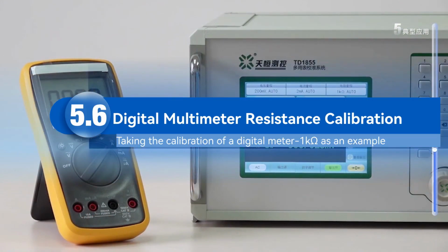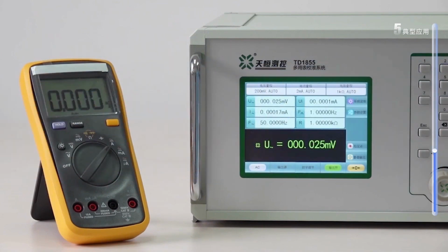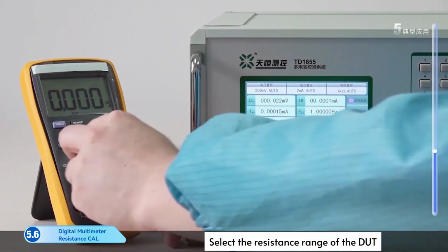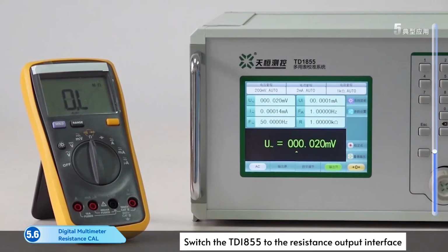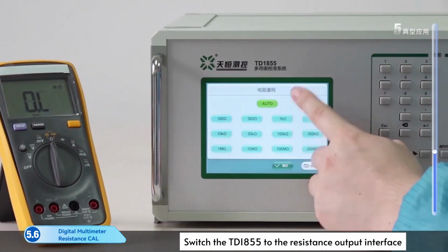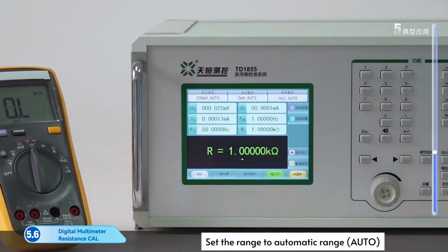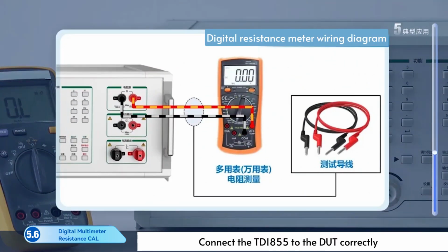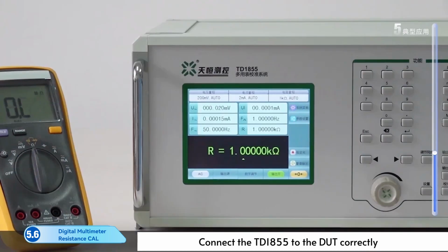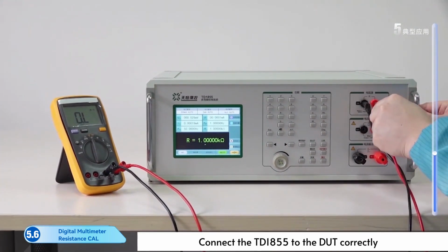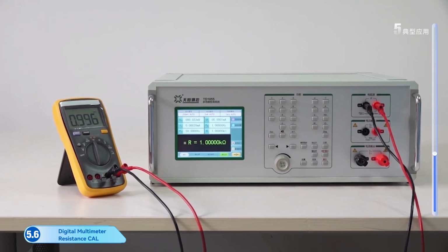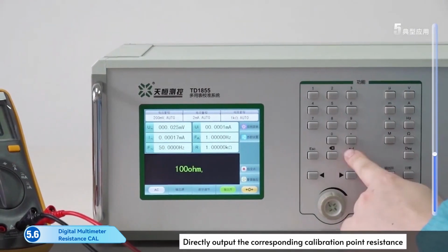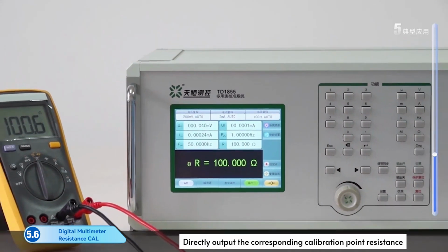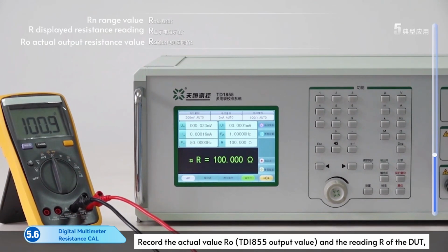Part 6. Digital Multimeter Resistance Calibration. Select the resistance range of the DUT. Switch the TD1855 to the resistance output. Set the range to automatic range. Connect the TD1855 to the DUT correctly. Directly output the corresponding calibration point resistance. Record the actual value and the reading of the DUT.